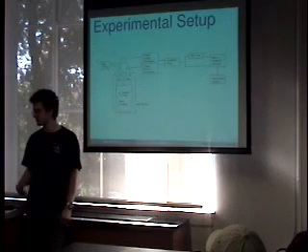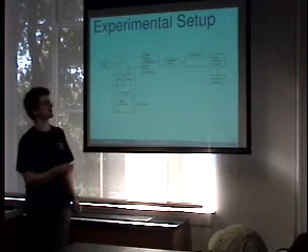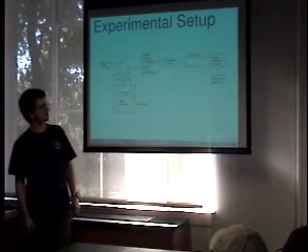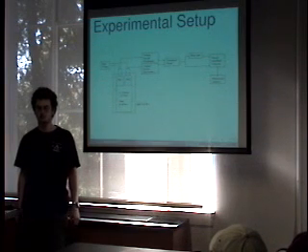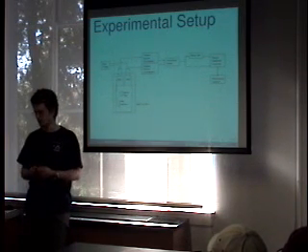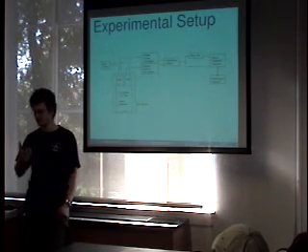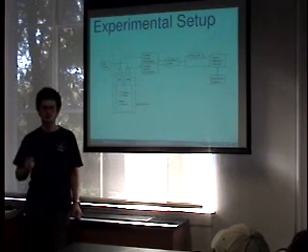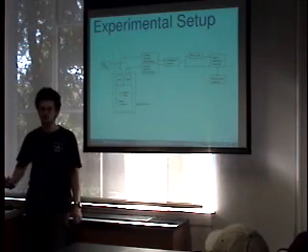And so the next step is that we take the output of the coincidence circuit and we send it into a time to amplitude converter, which takes the time between two signals and turns it into an amplitude, which is easier for computers to measure.